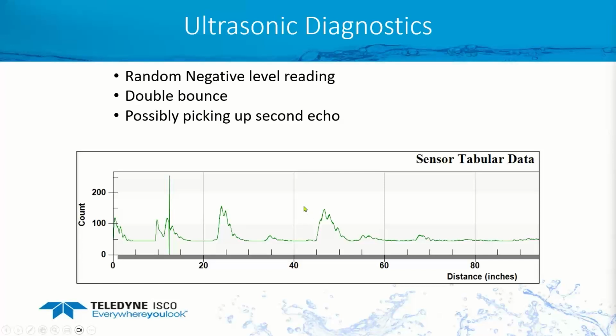So the way to get around that is, like on our equipment, you can actually adjust the blanking distance. So I can tell it I have a minimum of 1 foot blanking to the surface of the water, and a maximum distance of 40 inches. That way it focuses just on this area instead of that double bounce, and that's going to give you more accurate readings.